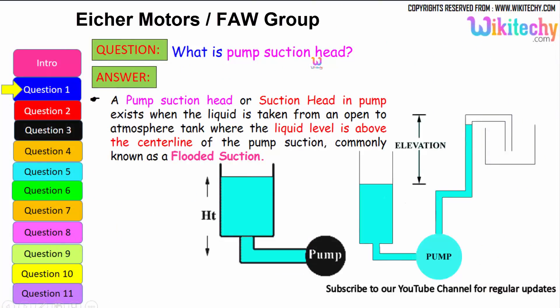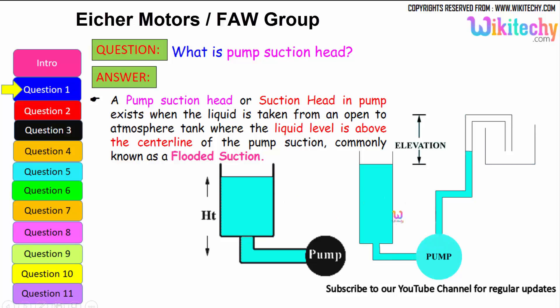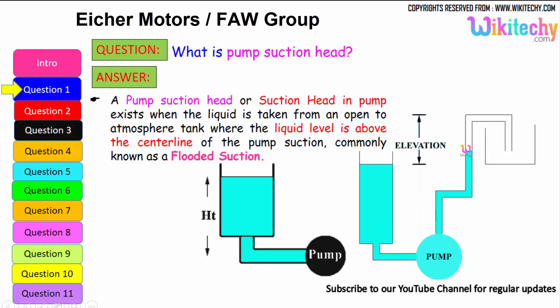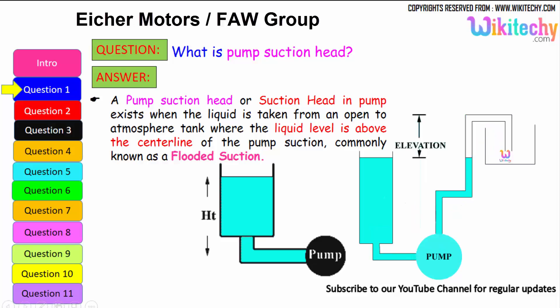What is a pump suction head? A pump suction head, or suction head in a pump, exists when the liquid is taken from an open atmospheric tank where the liquid level is above the centerline of the pump suction — commonly known as flooded suction. Automatically the pump suction will try to pick the water or any liquid from one area to the other area based on the atmospheric pressure.